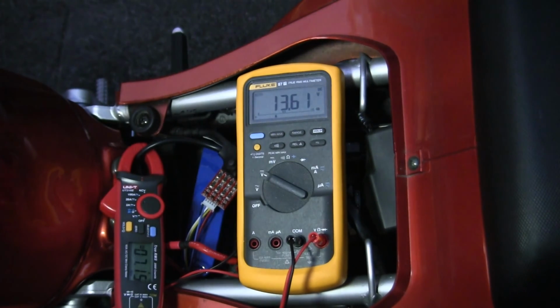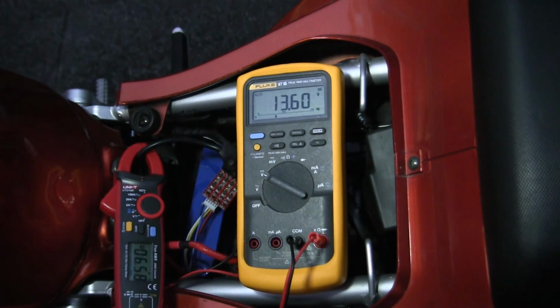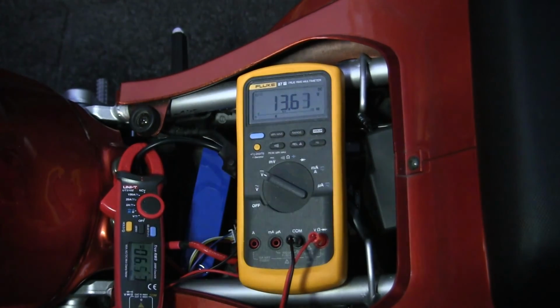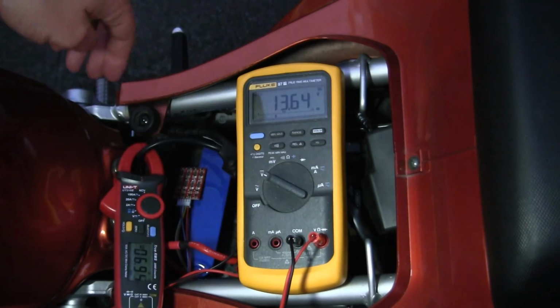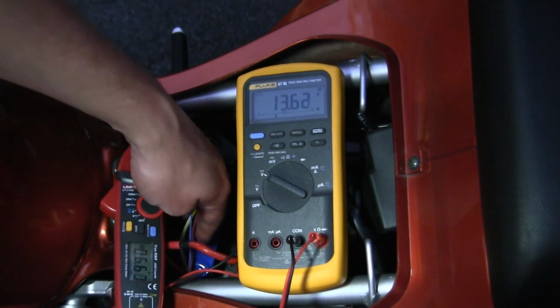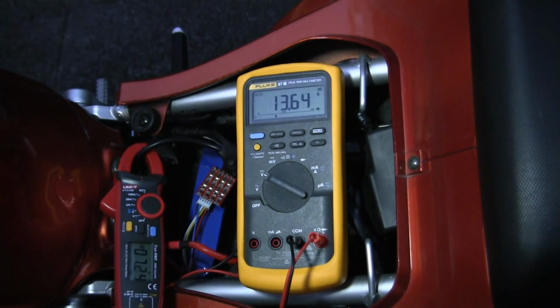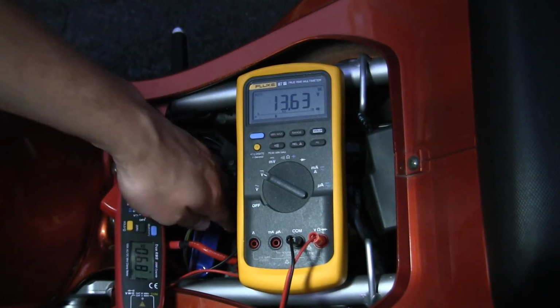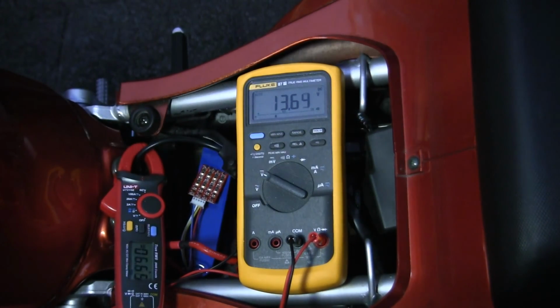The spec says that for lithium iron phosphate batteries, they are full when the voltage per cell is about 3.33 volts. But if you put more voltage on the cell, it will not cause damage. There are different papers out there - some say 3.65. I have a BMS that allowed the cells to go up to 3.85 volts per cell. 3.6 is 14.4 volts, 3.65 is 14.6 volts.